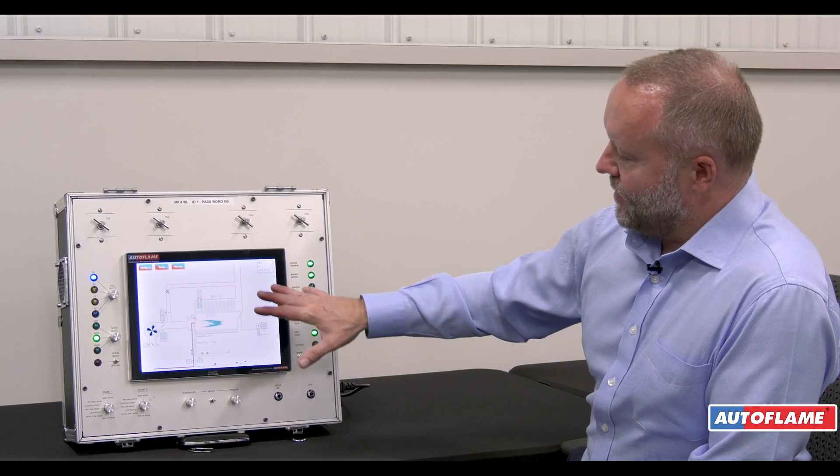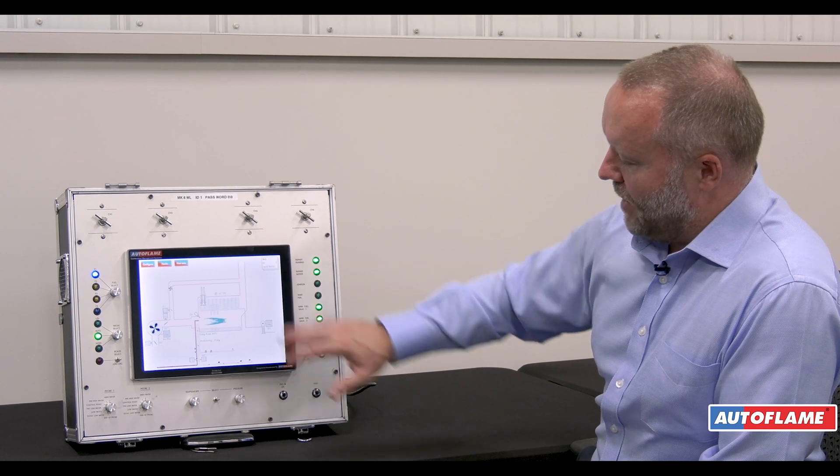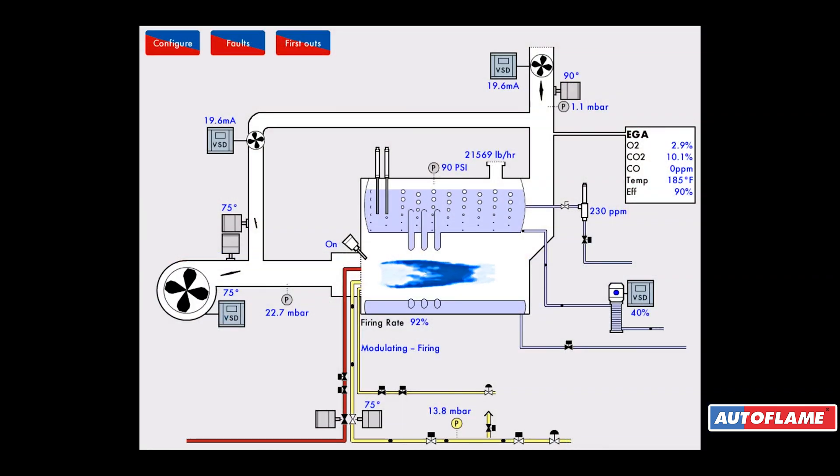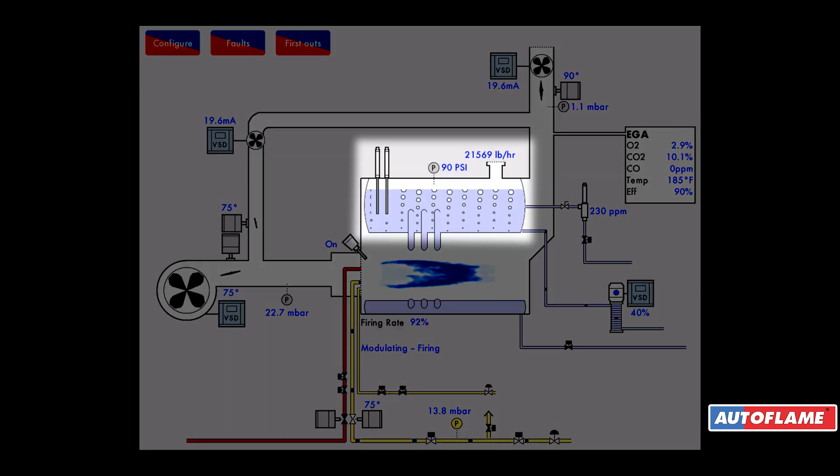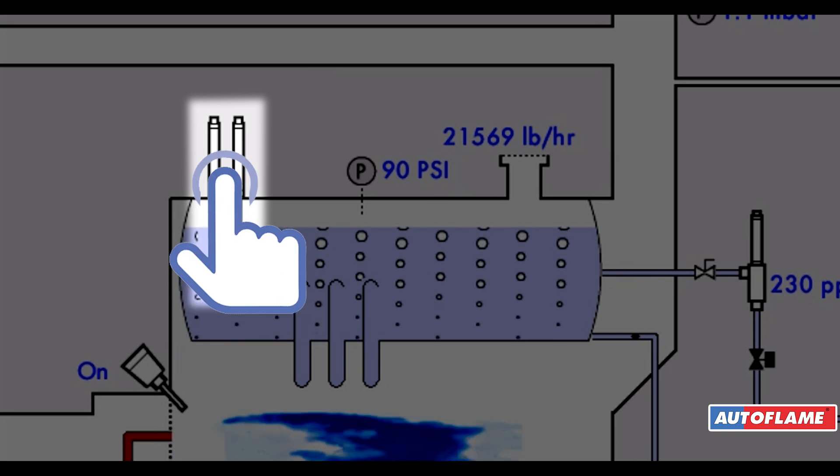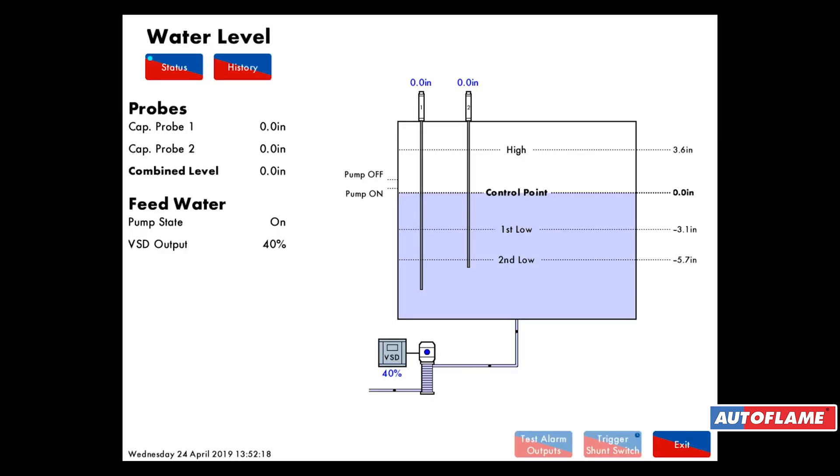Looking at this screen, we're looking at the water level side of the boiler. This is set up as a water tube, so we've got a mud drum down the bottom and a steam drum at the top. We've got two probes for looking at water level using capacitance probes.